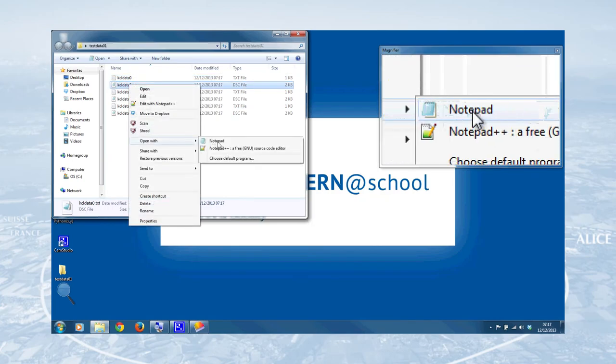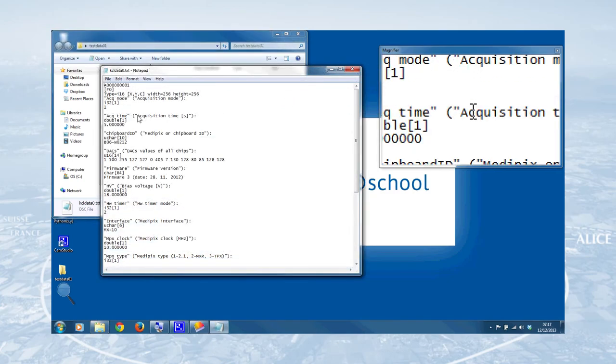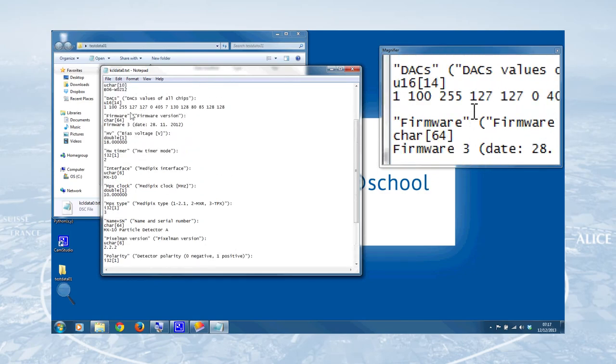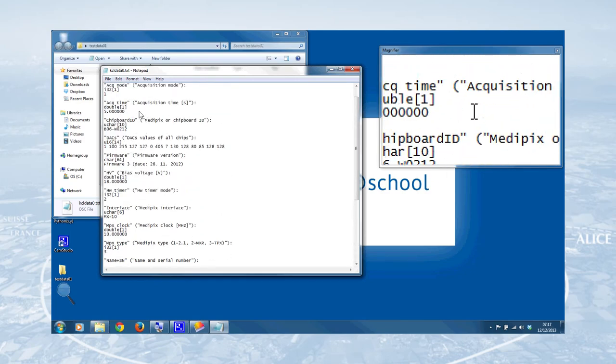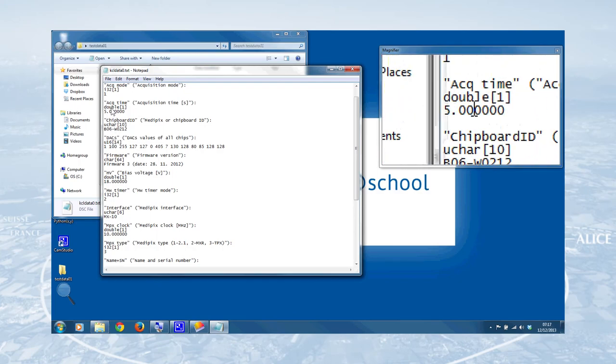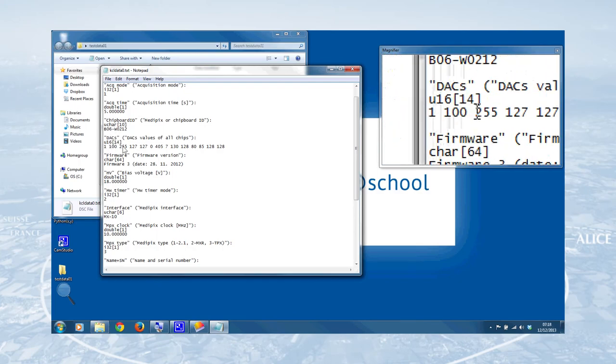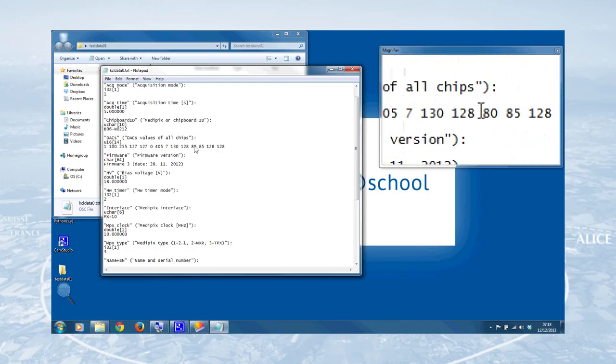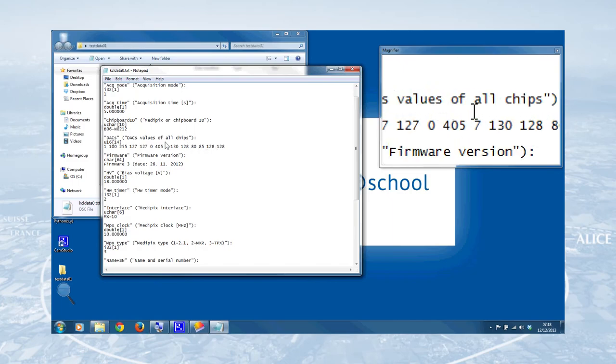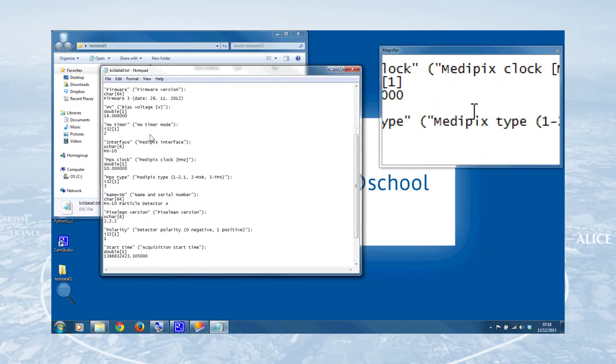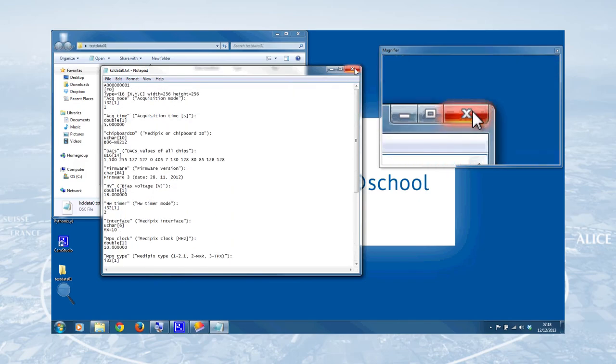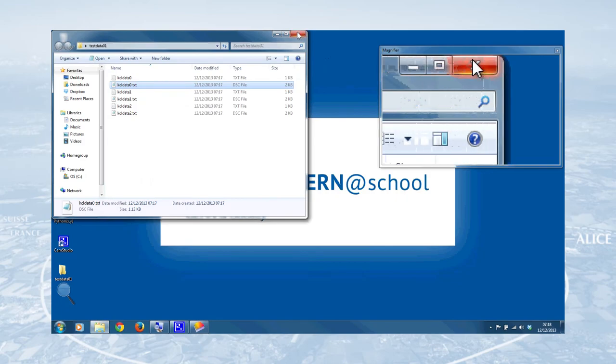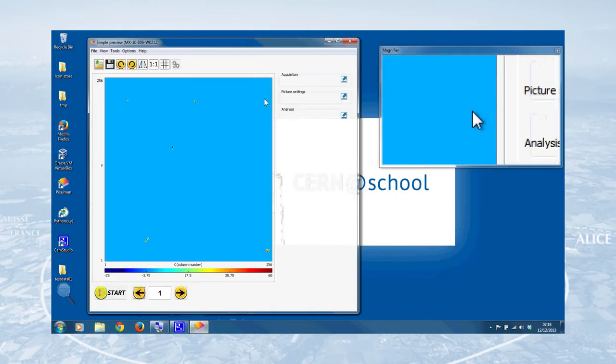But accompanying each of those, you've got a detector settings file, which contains all of the detector settings that were used while the detector was running. So you've got things like the acquisition time, that was five seconds, all of these detector settings here. And that's handy so that you don't have to write down what the detector settings actually were at that point. The computer all does it for you, which is very useful indeed. So we've got our data, we've got it saved, we've had a look at it.